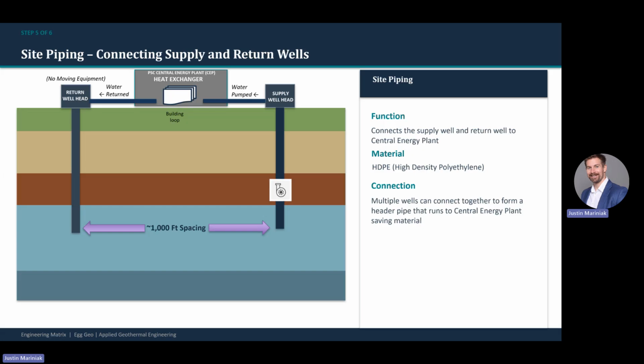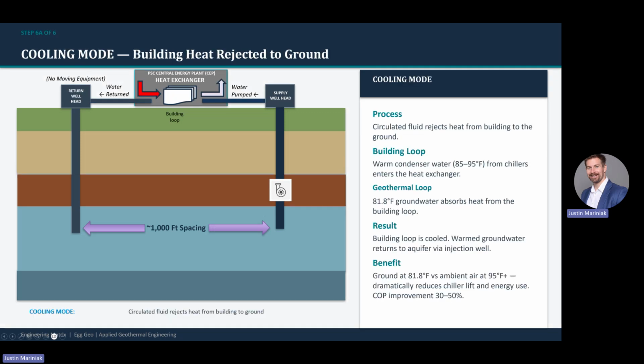To complete the loop, we need to connect the wells to the central plant. This is typically done via high-density polyethylene pipe. It is fusion welded and has a buried service life of 50 to 100 plus years. The public safety complex only uses geothermal for cooling. You can see the heat from the chiller is brought down through the heat exchanger and cooled down and returned to the chiller. The 81-degree groundwater absorbs the heat and then is returned to the ground. From an efficiency standpoint, compare this to an air-cooled chiller, which has to reject its heat to 95-degree plus hot summer air.